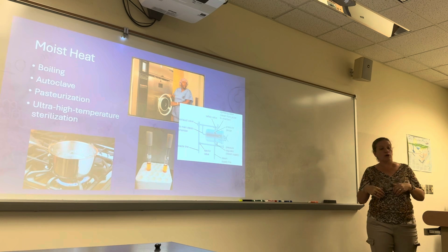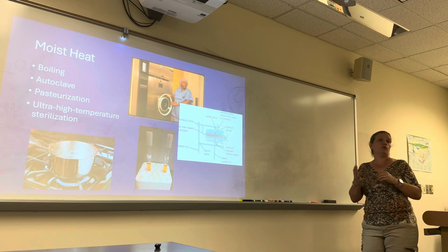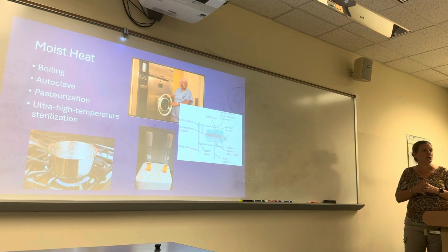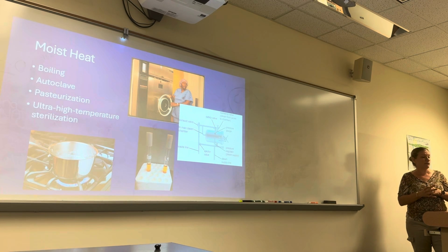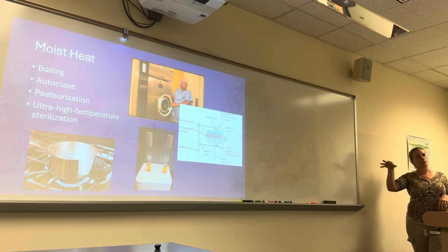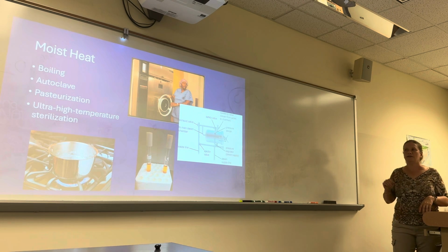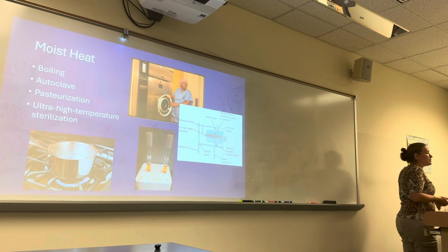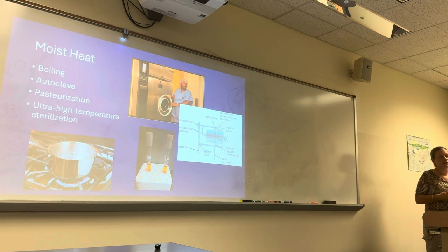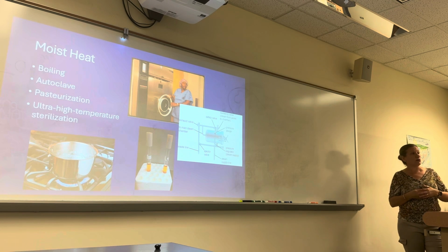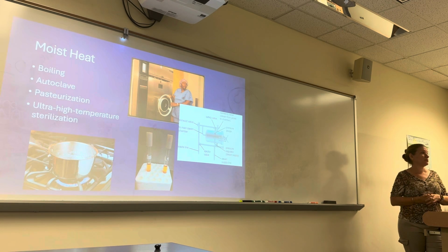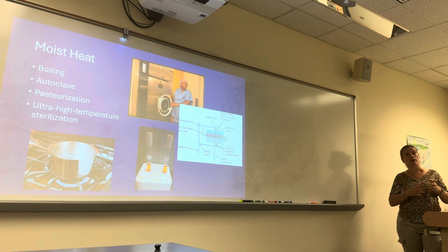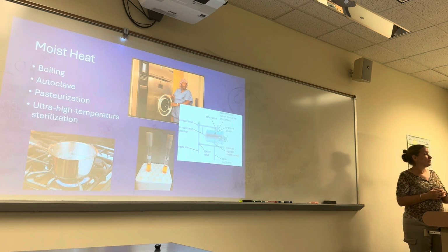In our lab, that regulation is once a month. Again, I don't know what a hospital setting has as far as regulations, but I know we are required to demonstrate on a monthly basis that not only are we looking at the tape and the printouts from the instrument saying everything's working well, but we also have another test. Because the goal here is to sterilize the biohazards that we don't want released into the environment or accessible to other people.